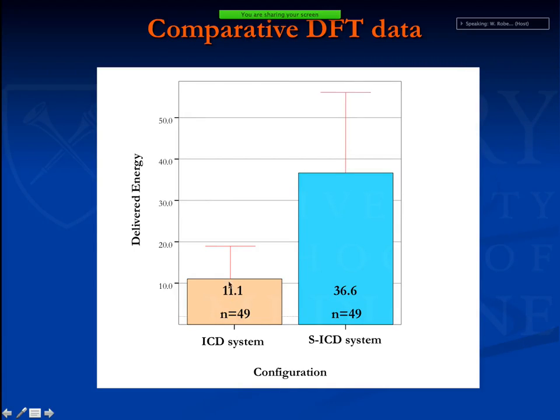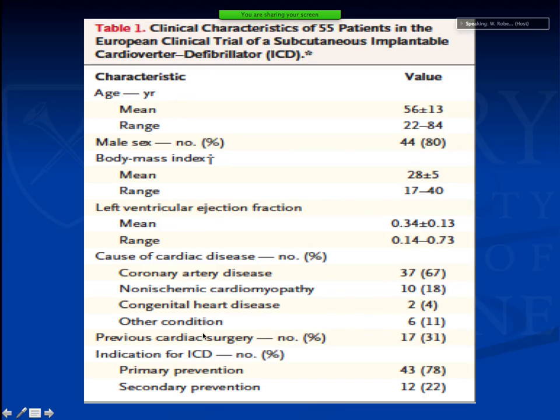And you can see that the mean DFT in the transvenous system is 11, and the subcutaneous system is 36. And remember, the subcutaneous ICD can deliver up to 80 joule. This device can deliver up to 35 joule. So still a little bit better of a safety margin with the transvenous ICD. And then they published the result of their European trial, which included 55 consecutive patients. So it's amazing how in Europe you get approval based on a very much smaller study than the US. They're not as strict in terms of their regulation.